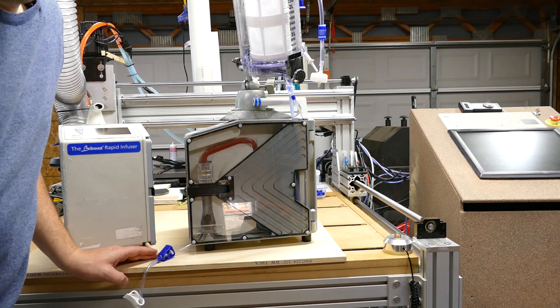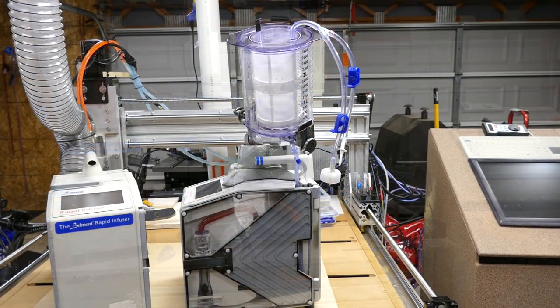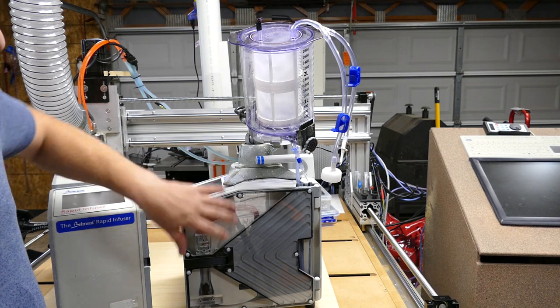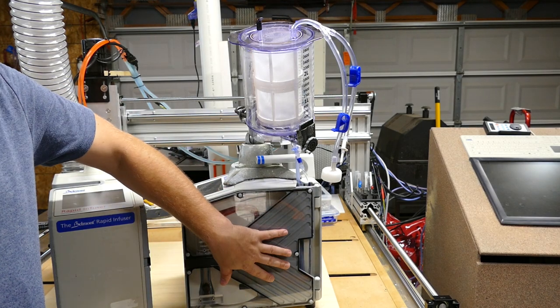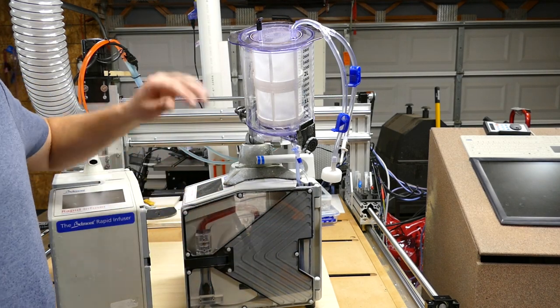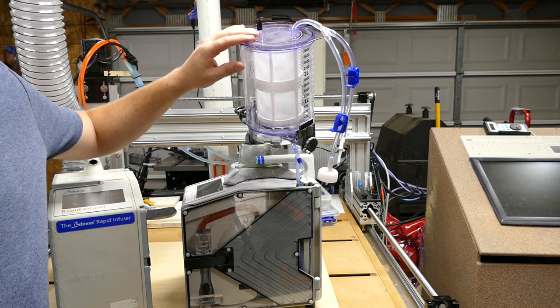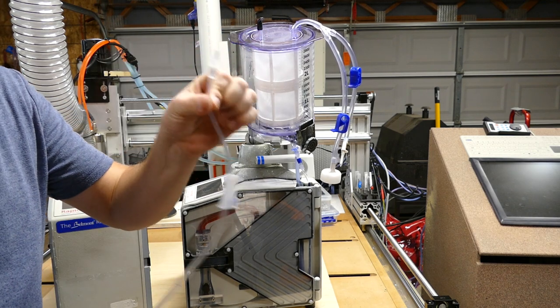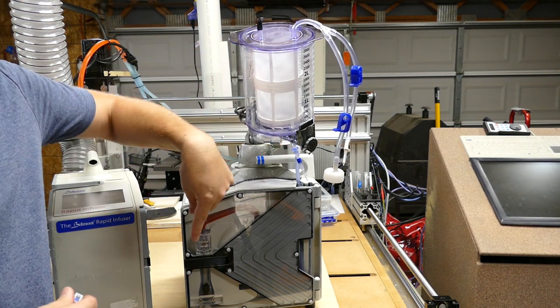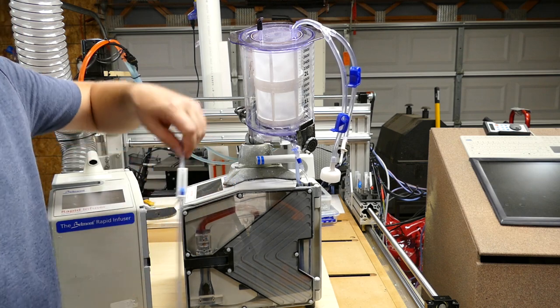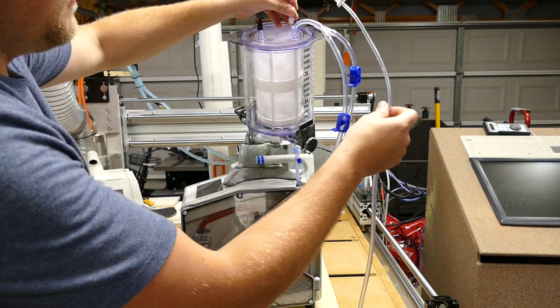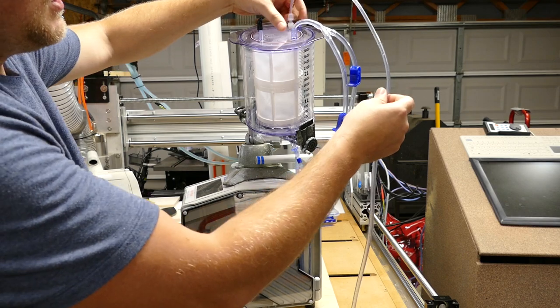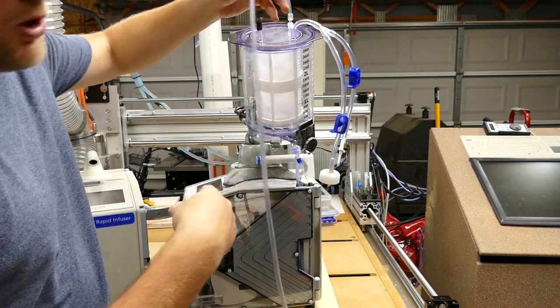And it's loaded up, ready to go. This sterile set comes in two pieces. One piece is the section that loads inside the device, and the second piece is your reservoir. So what you do is you take your patient line that runs out of the bottom corner over here. We're going to run it all the way up here to your vent cap in the top of the unit. And what we're basically doing is creating a closed loop.